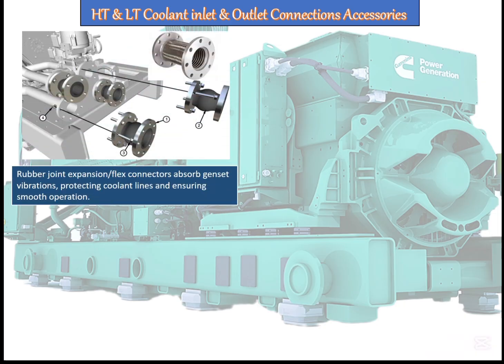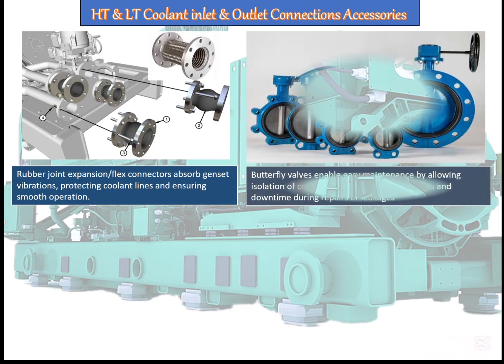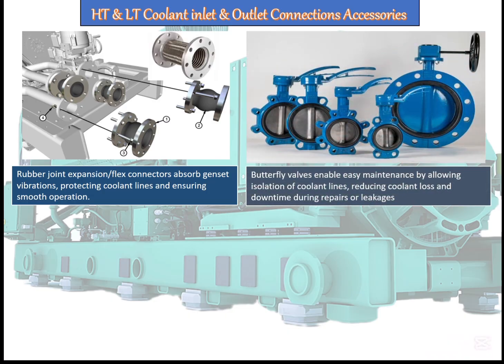Let's look at a bit more detail of the HT and LT connections. With the genset, once we do any kind of piping, we must use flex connectors. There are 2 types of flex connectors: one is rubber type and one is steel flex connector. You can supply either type, and we use them with the HT and LT cooling lines, the gas line and others. Then we also use butterfly valves. It makes maintenance easier.